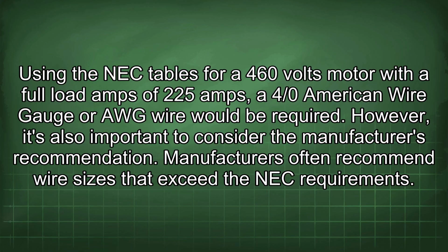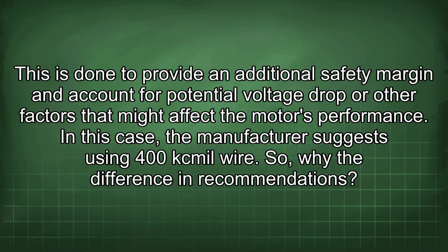However, it's also important to consider the manufacturer's recommendation. Manufacturers often recommend wire sizes that exceed the NEC requirements. This is done to provide an additional safety margin and account for potential voltage drop or other factors that might affect the motor's performance. In this case, the manufacturer suggests using 400 kcmil wire. So, why the difference in recommendations?